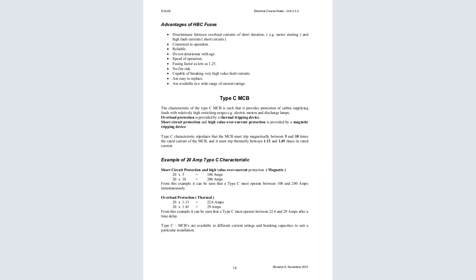As an example, for a 20 ampere Type C, we have the short circuit protection as high as 20 times 10, that is 200 amperes. From this example, it can be seen that the Type C must operate between 100 to 200 amperes instantaneously. For overload protection, that is the thermal, it is 20 times 1.1, that is 22 amperes. So the Type C must operate at 22 amperes and above after a time delay. The Type C MCBs are available in different current ratings and breaking capacities to suit the particular installation.